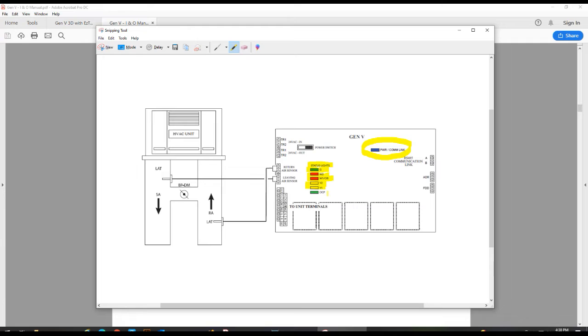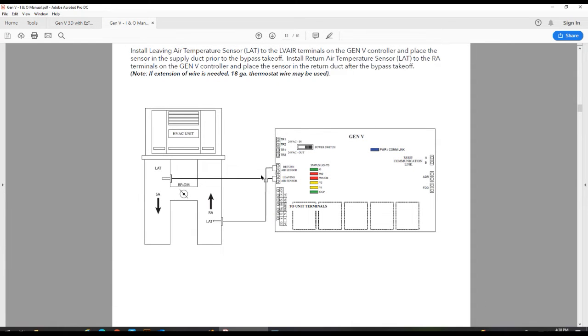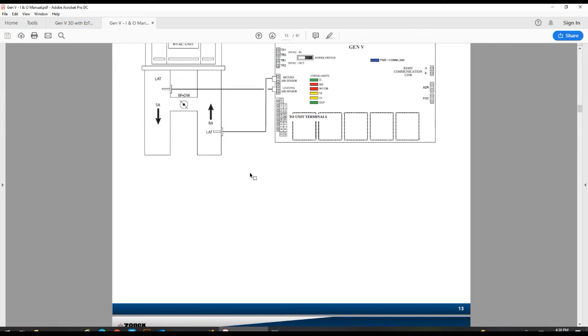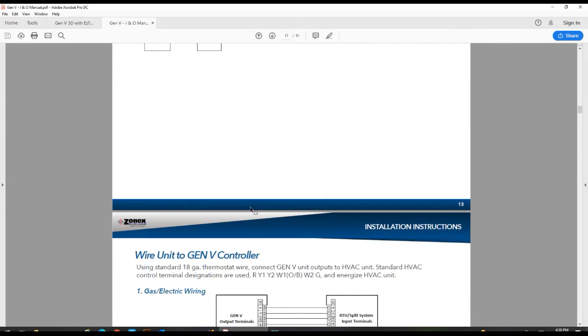And then we have a secondary green light at the bottom that says OCP, and that is lit when the system is in occupied mode. If you're running economizers or anything that utilizes an OCP terminal, you can wire that up, and that will bring your economizer awake or occupied and start running its designated settings it's been given.